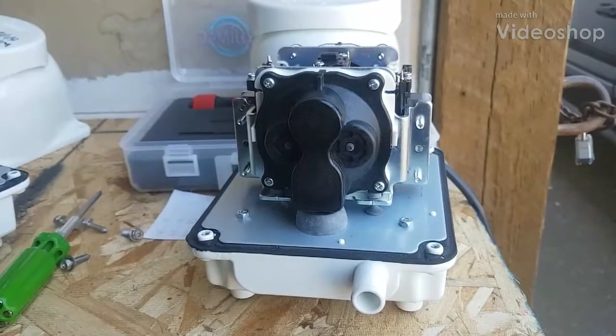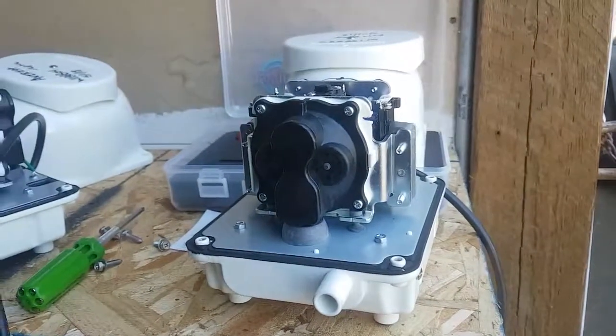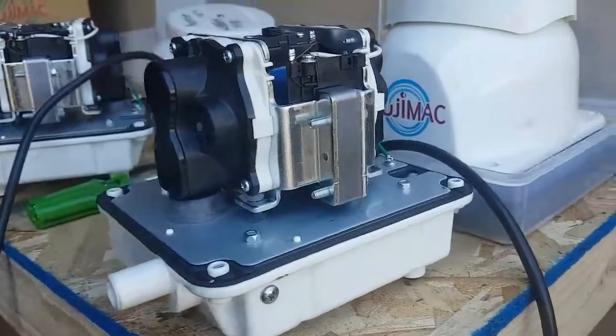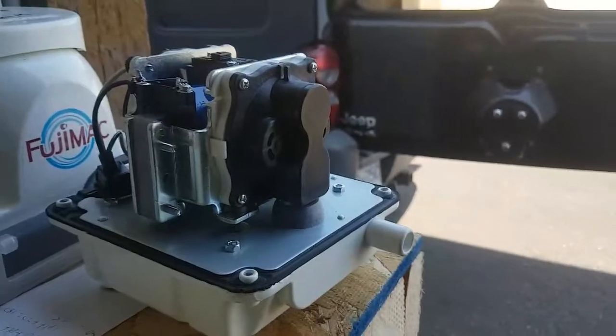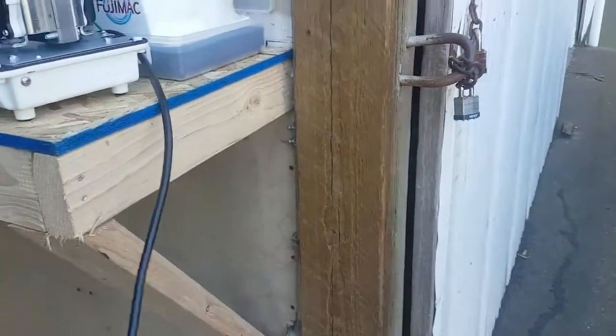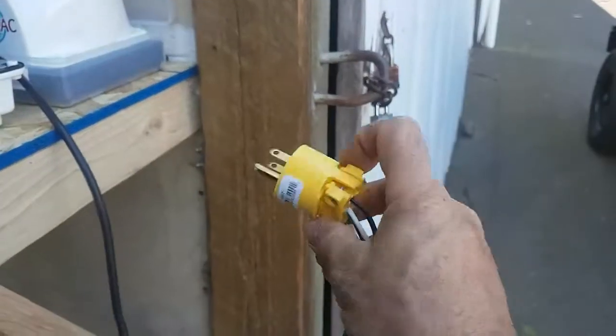This is a FujiMac 80 R2 pump that's been returned for warranty. The concern is that it's not pumping air. I've taken the housing off and it all looks good. I've had to wire a new plug-end on to test it because a lot of people cut the plug-end off to hardwire them into a control panel, which is fine.